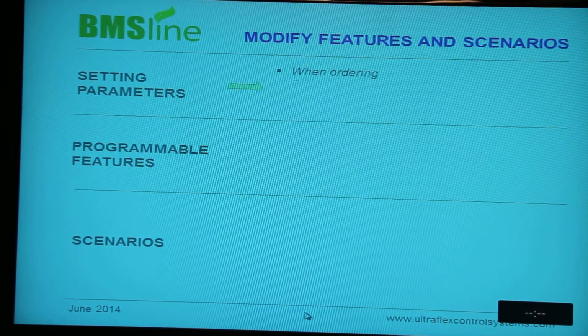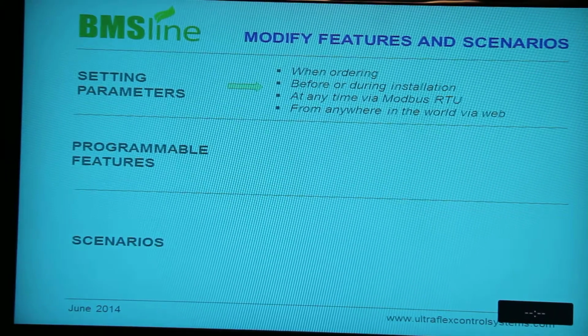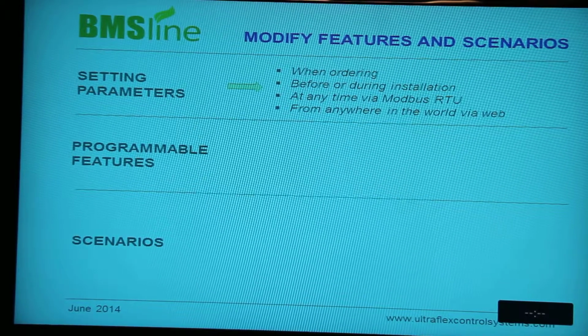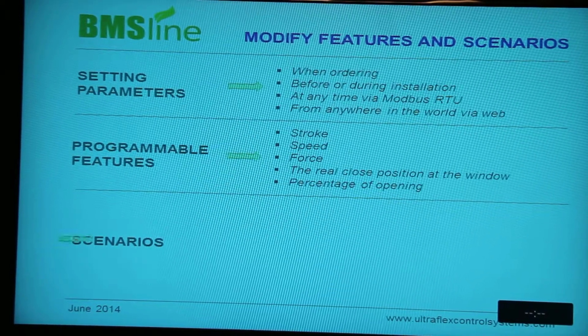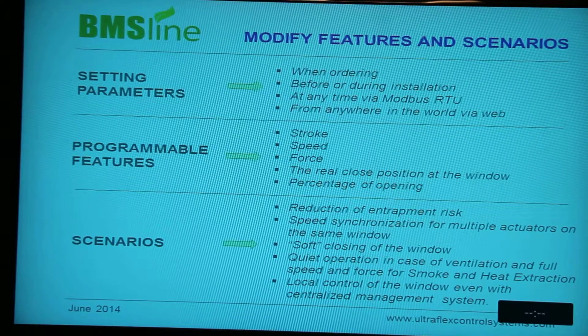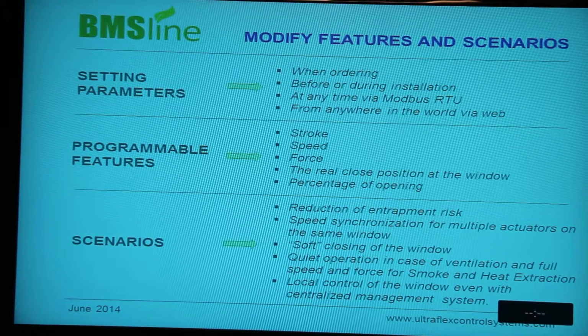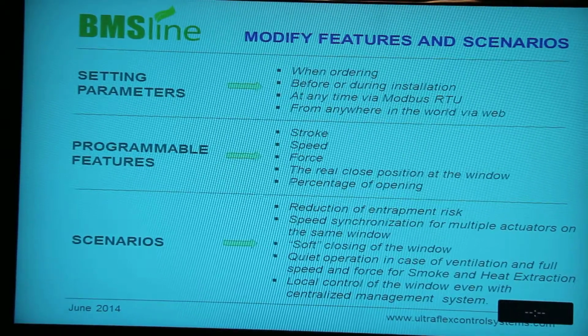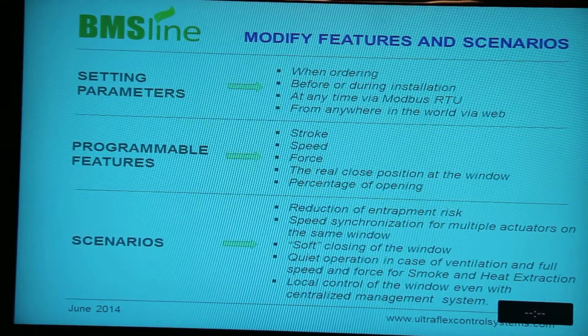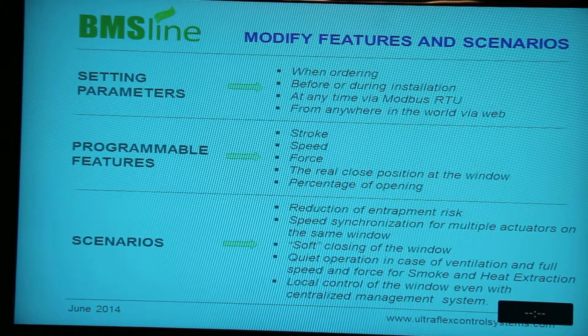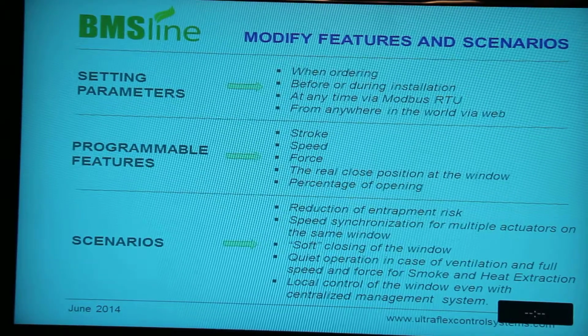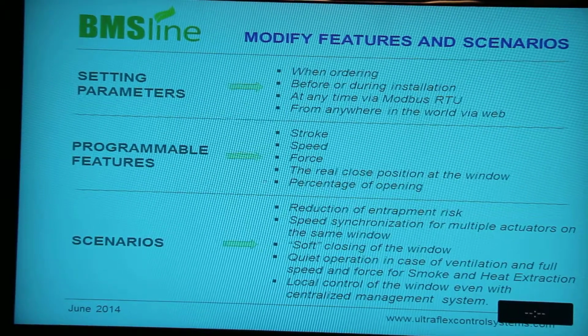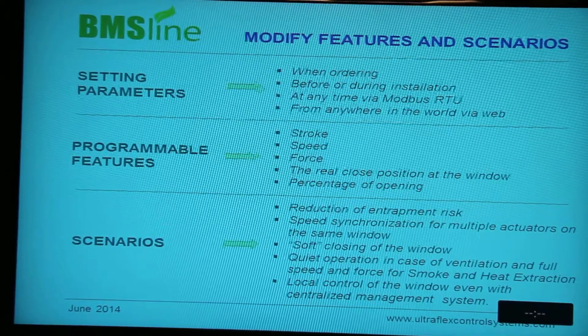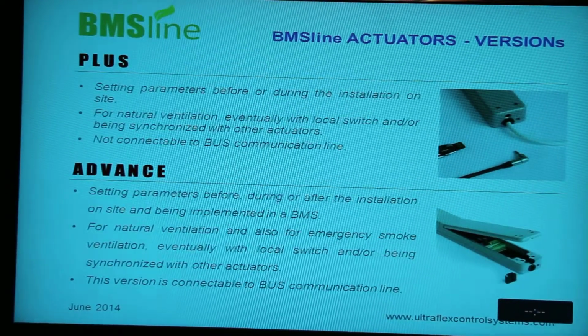We start off with setting the parameters when ordering, before or during the installation, at any time via Modbus RTU from anywhere in the world via the web. These are the programmable features: the stroke speed, force, the real close position of the window, percentage of opening, and scenarios like reduction of entrapment risk, speed synchronization for multiple actuators on the same window, soft closing of the window, quiet operation in case of ventilation, and full speed and force for smoke and heat extraction, local control of the window system with centralized management system.